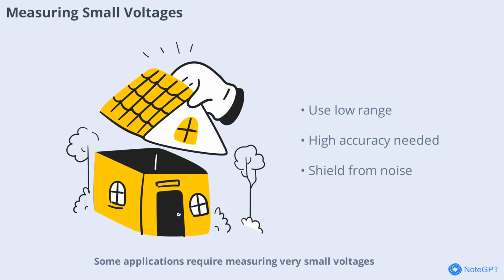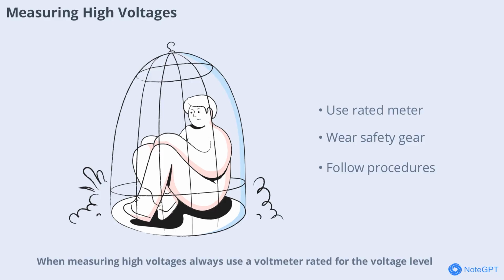Some applications require measuring very small voltages, such as in sensitive electronic circuits. Use a voltmeter with a suitable low voltage range and high accuracy. Shield the circuit from electrical noise to get the most precise readings possible. When measuring high voltages, always use a voltmeter rated for the voltage level. Wear appropriate safety gear and follow all safety procedures. High voltage measurements are common in industrial and utility settings, and safety cannot be overemphasized.